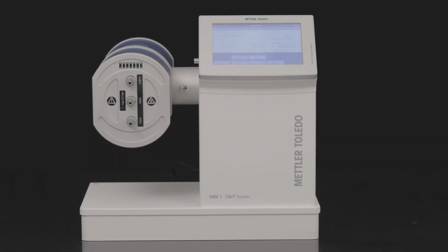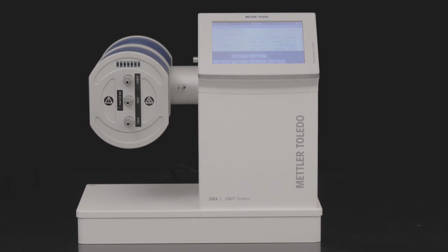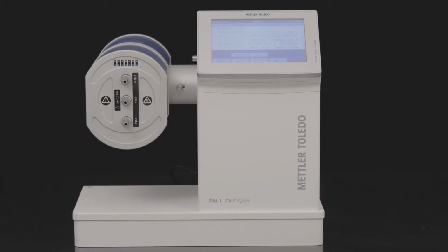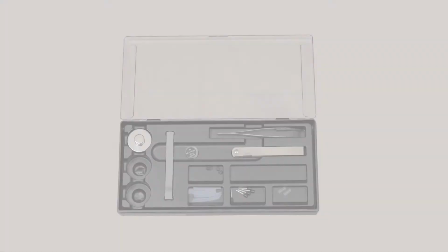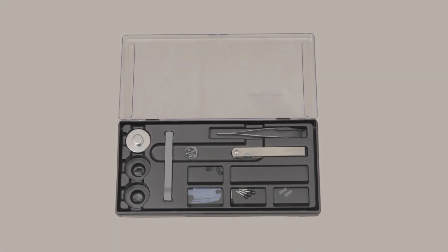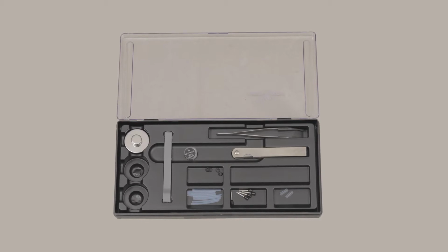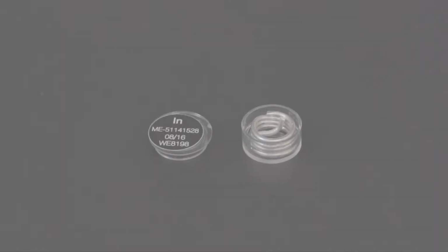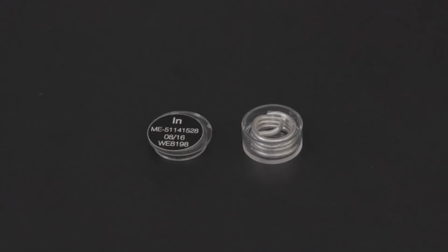The DMA temperature calibration procedure is based on ASTM E1867. It is highly recommended to perform the temperature calibration using a certified reference material, such as indium wire, which is supplied by Mettler-Toledo as a DMA accessory.